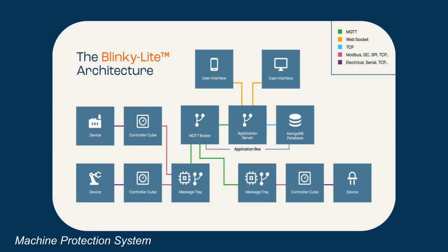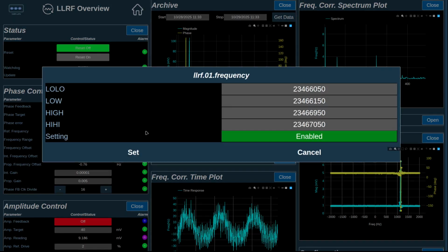It uses named values called cubes, which often store scalar data. Attached to a scalar cube is an alarm block. This block defines 4 key limits. Low and high settings act as warning limits. The low-low and high-high settings are the error limits.